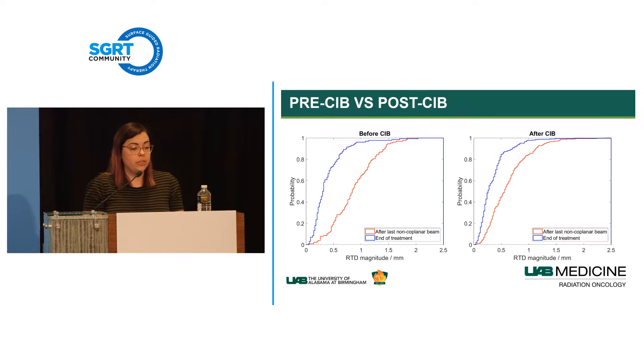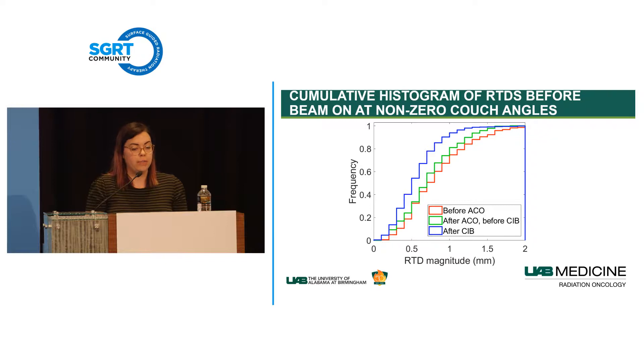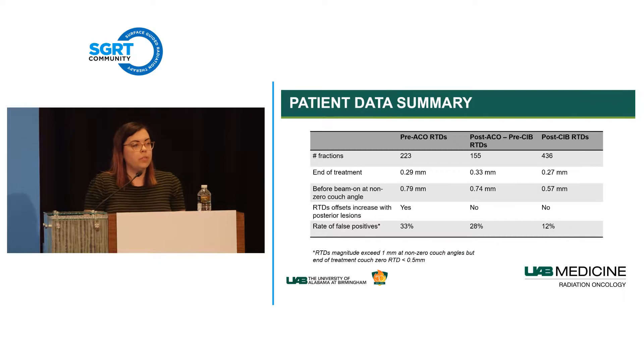Looking at patient data: probability maps of RTD magnitude show that after implementing the CIB cold calibration, the distributions at end of treatment and after the last non-coplanar beam are much closer together. Comparing all three time periods, we got the largest improvement with the CIB calibration protocol. The median end-of-treatment RTD dropped to about 0.27 mm, we no longer had isocenter-location dependence, and our false positive rate dropped to about 12%.